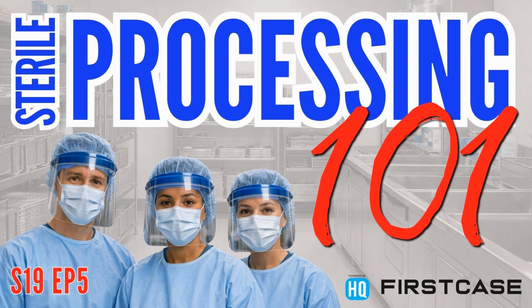And sterile processing departments often grumble about how much their low-temp sterilizer fails. And most of the time, it's because the person loading the sterilizer or putting something together in prep and pack included something that wasn't supposed to go in there, or the instrument wasn't all the way dry, or something like that. The cycle, because it's not hot and because it's not wet, there isn't really a cool down period, though. So even though the cycle itself may take a similar amount of time, it might be in the chamber only for, say, 45 minutes, 30 minutes. But whenever the chamber opens up, the instruments are immediately available for use. Oh, that's so nice. That's an upside to it.